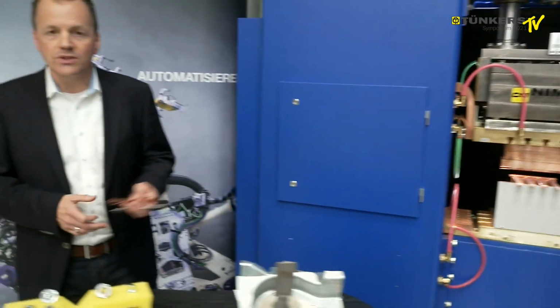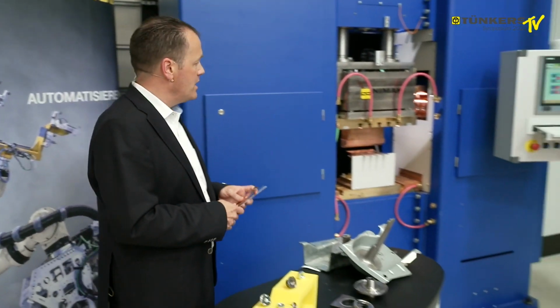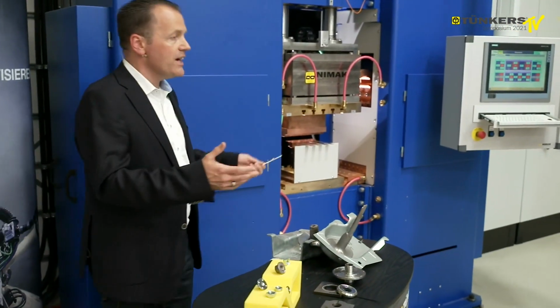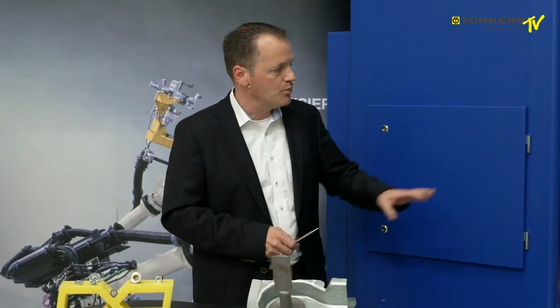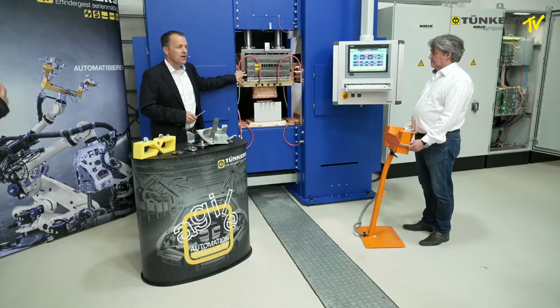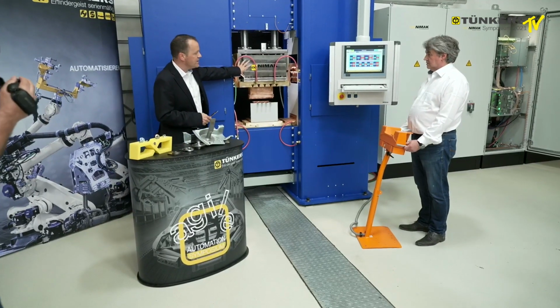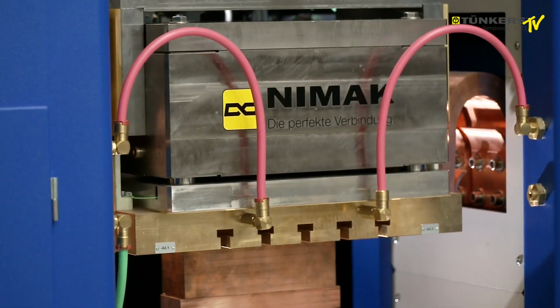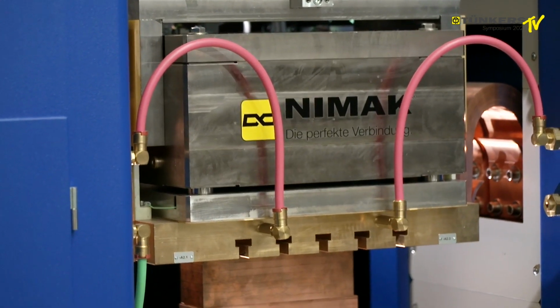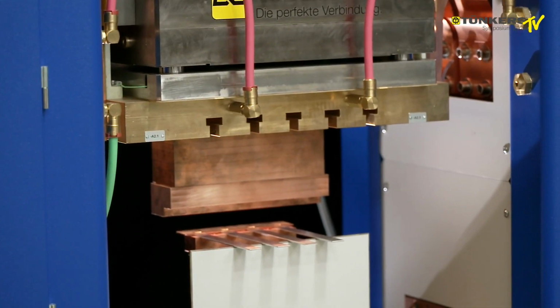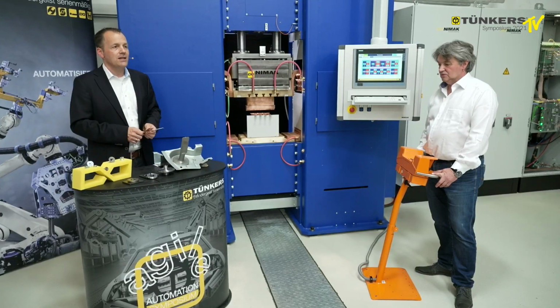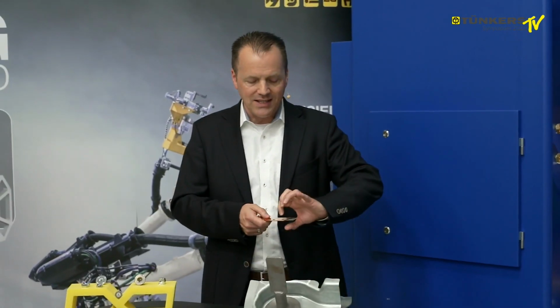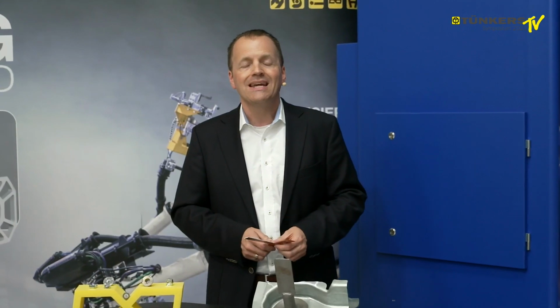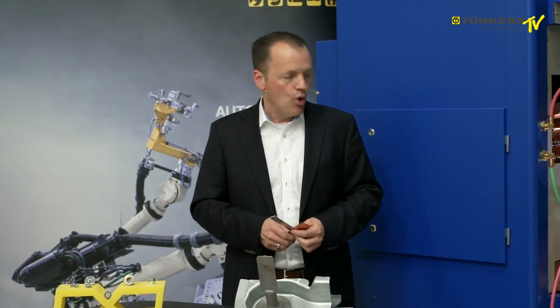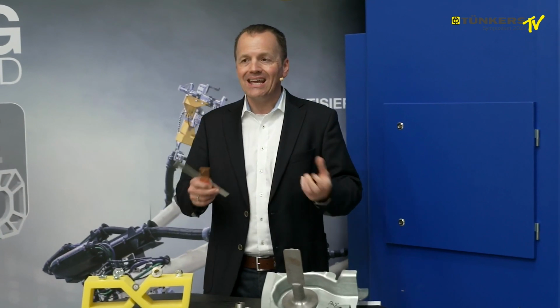Okay, in order to show you the most important parameters of this machine, we can have welding currents completely controlled for all profile types up to 200 kiloamperes. On top of that, we have magneticDRIVE technology used here, which is a highly dynamic actuator on a magnetic base, which means that during the actual welding, the welding force that we need for the repositioning of projection welding can be controlled at any time and adjusted.